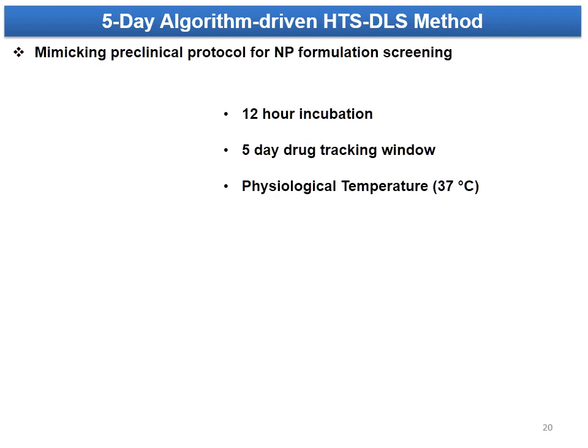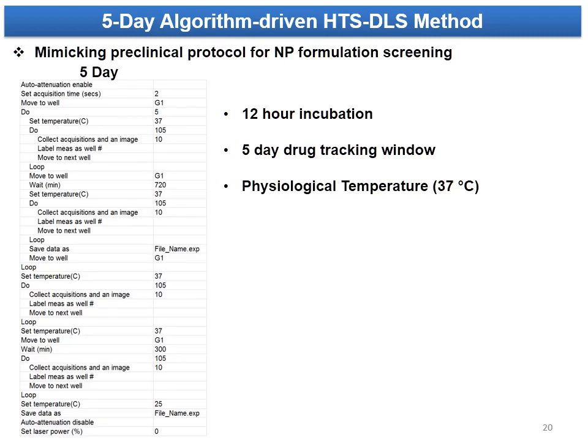The slide shows instrument-generated photographs of wells captured on day 1 and on day 5 of the nanoparticle size measurement experiment performed at 37 degrees Celsius. This photographic process can help identify outliers such as air bubbles in the datasets. Along with the autocorrelation function, you can use this functionality to single out outliers. The algorithm was designed to test stability and aggregation of nanoparticles in BSA medium over a period of 5 days, assuming the nanoparticles are used as drug carriers that take around 12 hours to be internalized into target cells at 37 degrees Celsius and deliver drug over 5 days.